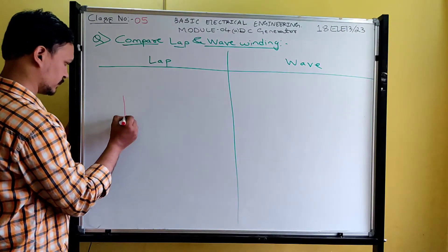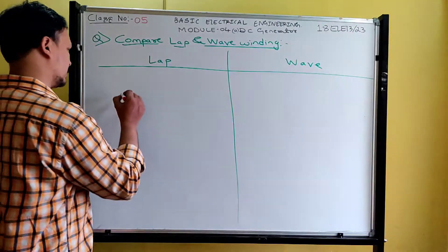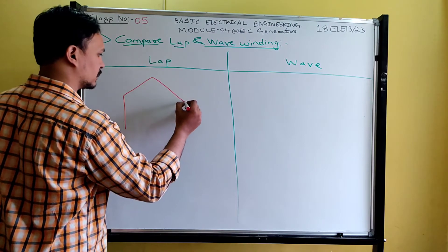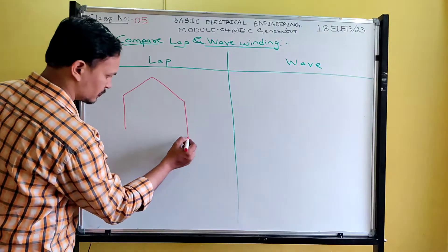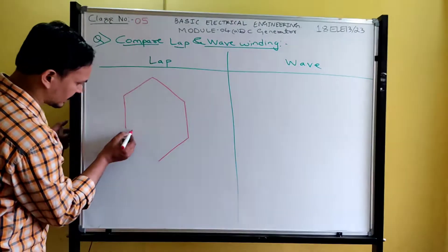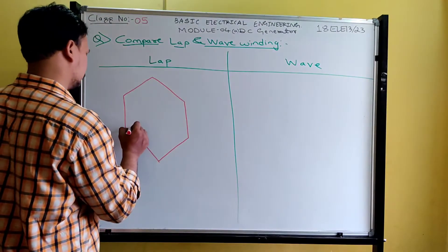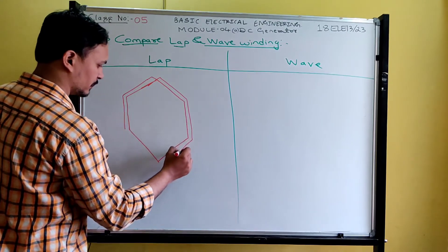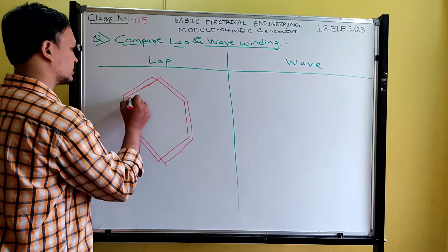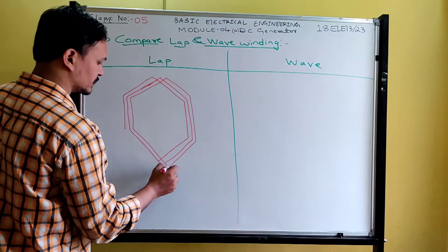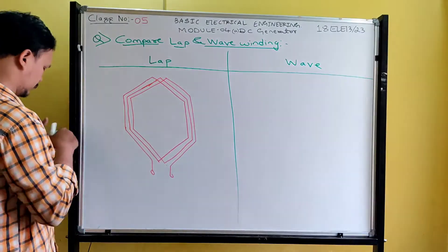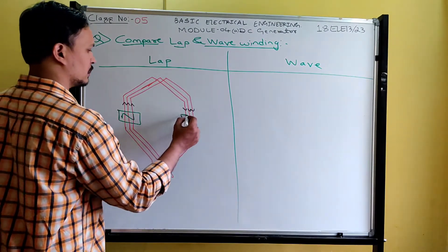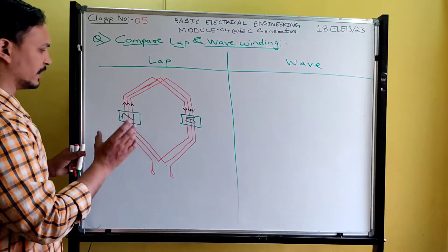Please observe carefully. For lap winding, this is the first conductor — let's say it is the first conductor of the north pole. This is the starting end and this is the finishing end. The finishing end of the first north pole conductor is connected to the first south pole conductor, and the finishing end of the south pole conductor is connected back to the second north pole conductor. Between the poles, the winding is overlapped. Group all conductors under north pole and all conductors under south pole — this is the winding arrangement for lap winding.